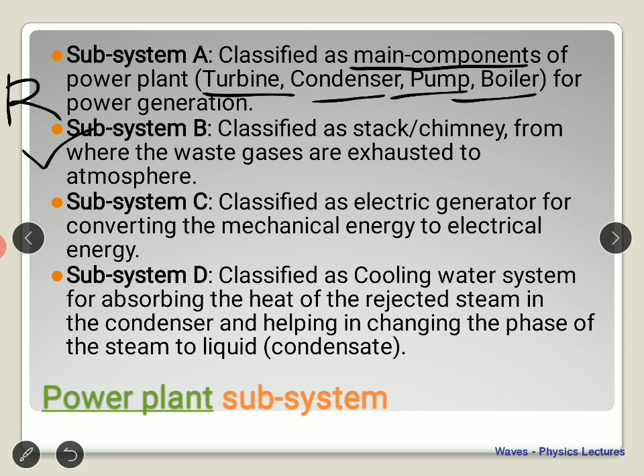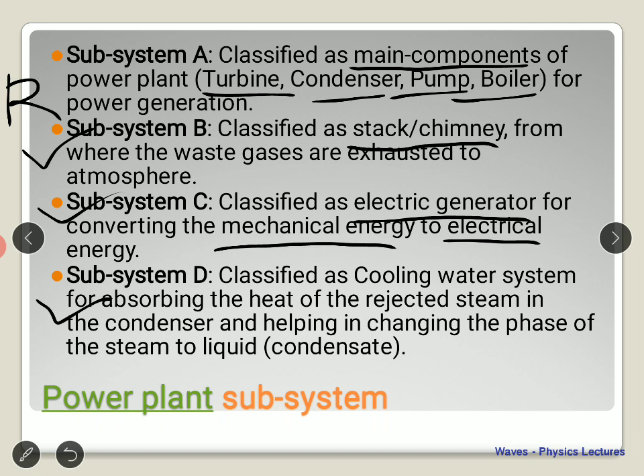Subsystem B is basically something which throws out the excess exhaust, connected with the stack or chimney. Subsystem C is the electrical generator — that's where we convert mechanical energy into electrical energy, which we discussed as the alternator last class. Subsystem D is classified as the cooling water system, which absorbs the heat of the rejected steam — the water is cooled down and then heated up again to generate more steam.